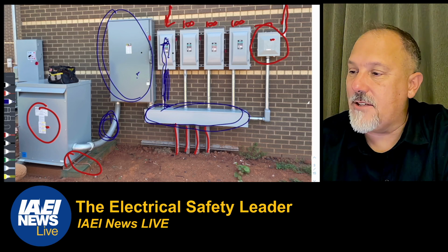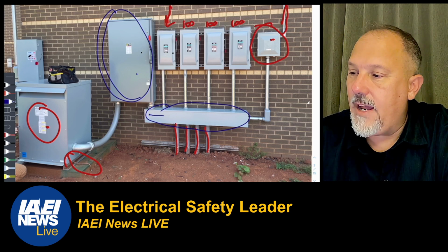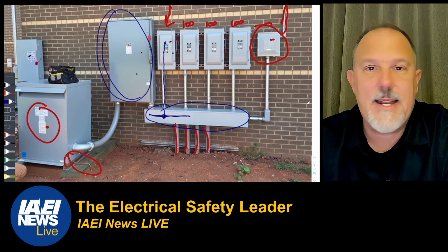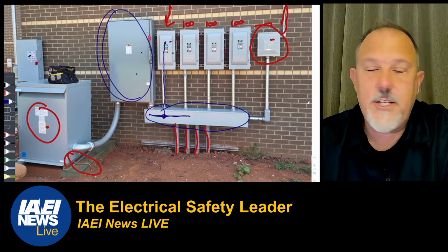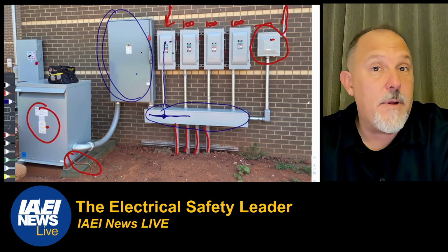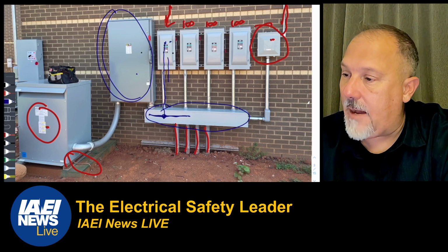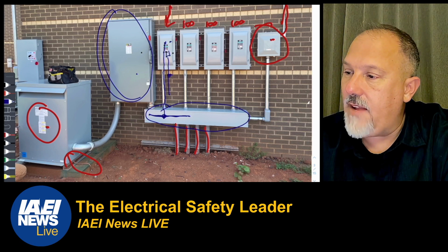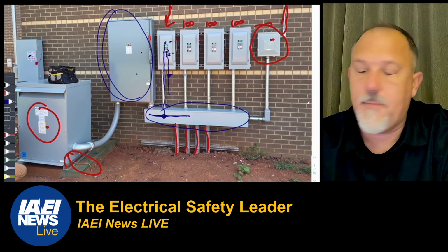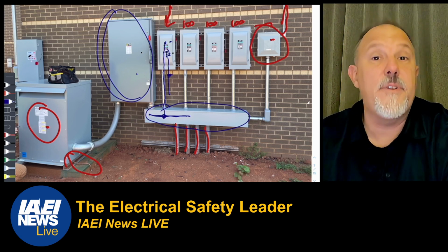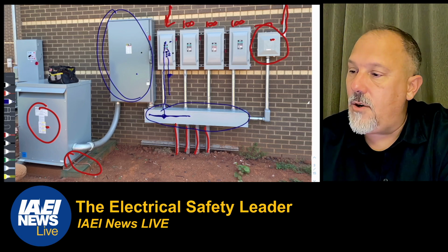So what does this tap conductor do? Right? This tap conductor, so I have a conductor here. I tap it, I bring it up, and I land on the high side of that fusible switch, and that's the length of the tap. Because everything past the tap is a feeder. So remember, I have a fuse right there. That fuse is providing protection. Now I'm into a separate feeder. My tap is only from where I've tapped in here and up.